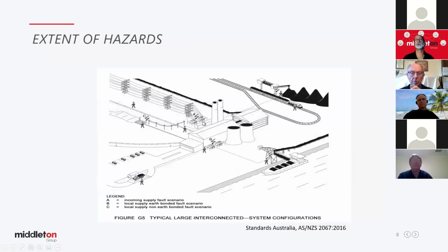This is just to show the extent of how far an EPR can be transferred. So if we've got a fault at the substation here at this industry, if all the plant's bonded and we've got supplies bonded out to ship loaders and up to coal loaders, etc., a fault here can transfer hazardous voltages out many metres, many hundreds of metres. So you don't need to be next to the substation to experience a touch voltage and an electric shock.